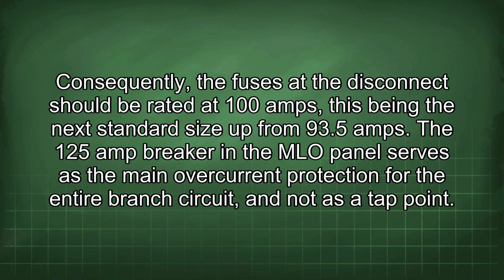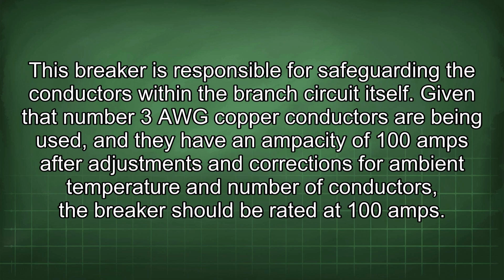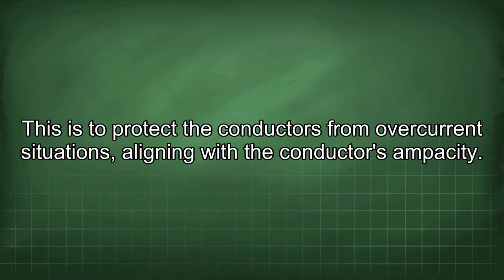The 125 amp breaker in the MLO panel serves as the main overcurrent protection for the entire branch circuit and not as a tap point. This breaker is responsible for safeguarding the conductors within the branch circuit itself. Given that number 3 AWG copper conductors are being used, and they have an ampacity of 100 amps after adjustments and corrections for ambient temperature and number of conductors, the breaker should be rated at 100 amps. This is to protect the conductors from overcurrent situations, aligning with the conductor's ampacity.